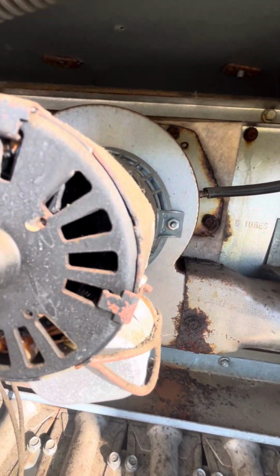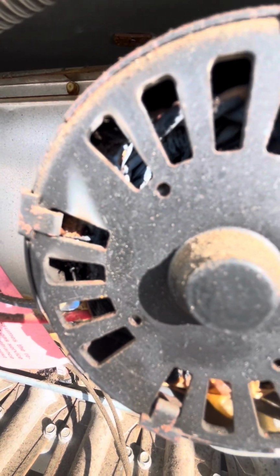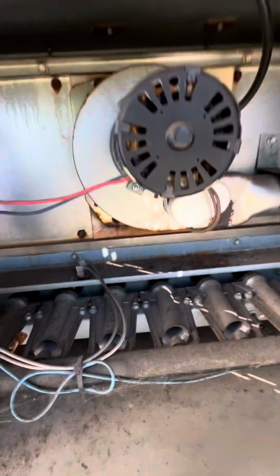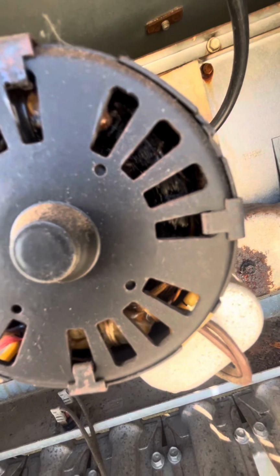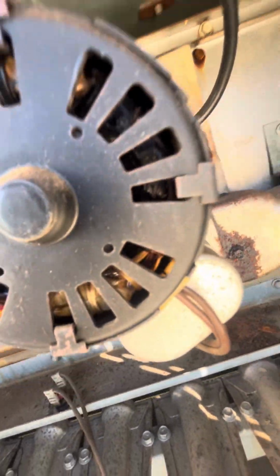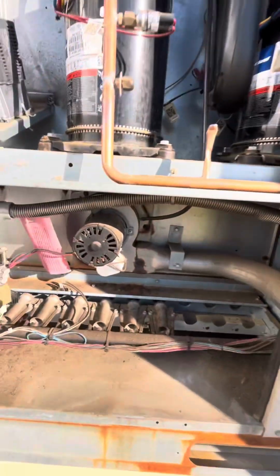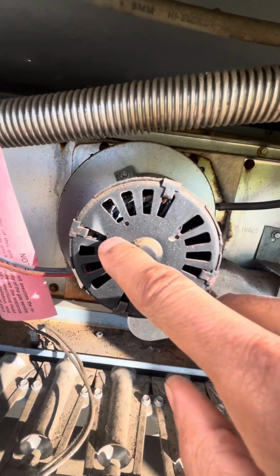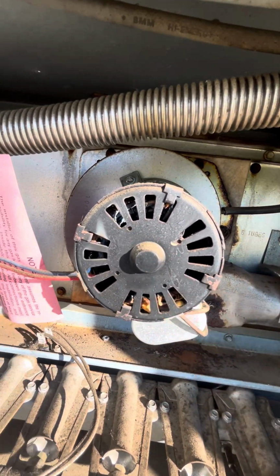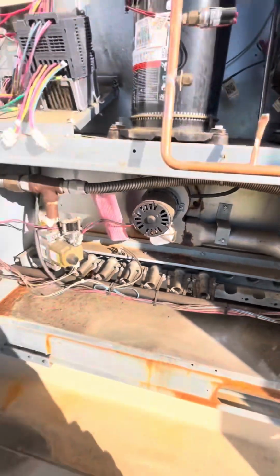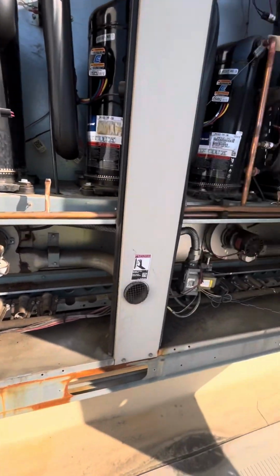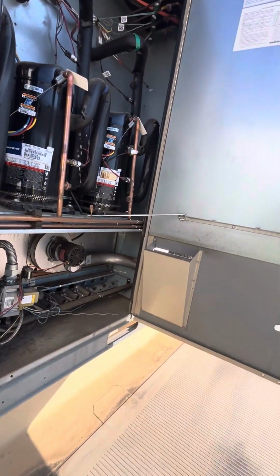If I'm looking at my windings, those are windings in there. It's a bunch of coils. And that is evidence of burn wires and coils. You should want to see like a brownish color on your windings. This one look kind of black. But I'm not gonna condemn nothing until I know for sure. I can almost go ahead and condemn this one because you see this here, like it's been shorted out already. But that's just a visual inspection without checking anything. I ain't checked nothing yet.